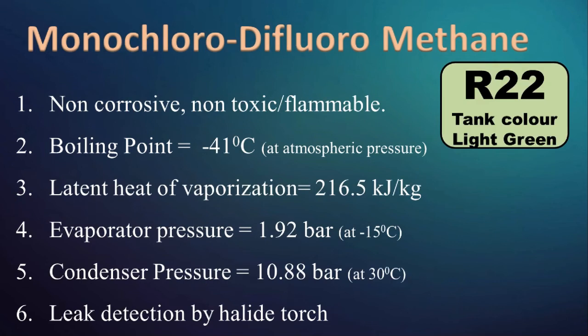R22, Monochlorodifluoromethane, is non-toxic, non-corrosive, non-irritating, and non-flammable. It has a boiling point of minus 41 degree Celsius. The latent heat of vaporization of R22 is 216 kJ/kg. It has evaporator pressure of 1.92 bar and condenser pressure of 10.88 bar. Leak detection of R22 can be done by Halide torch or electronic leak detector. The storage tank color for R22 is green. R22 finds applications in fast freezers and low temperature applications.